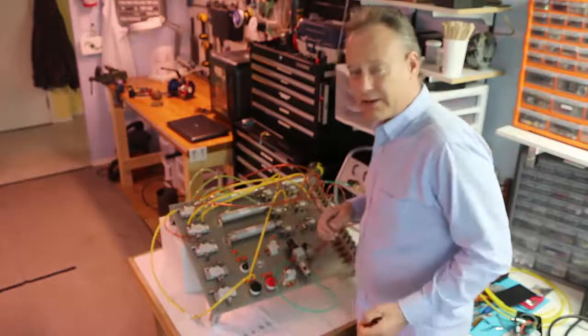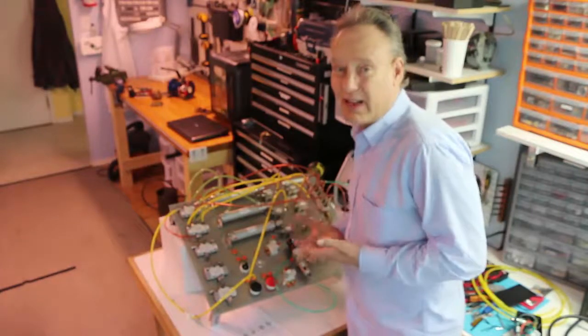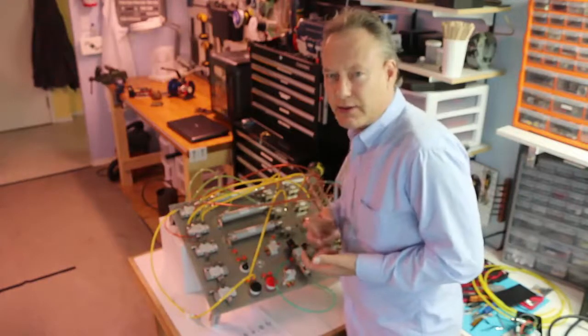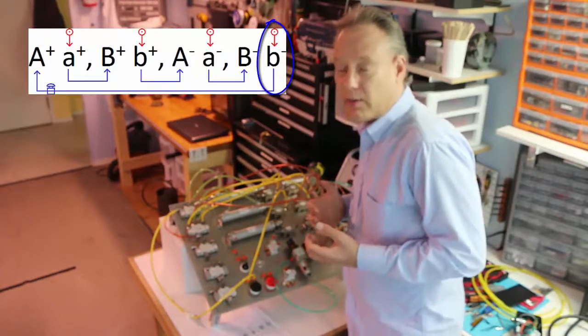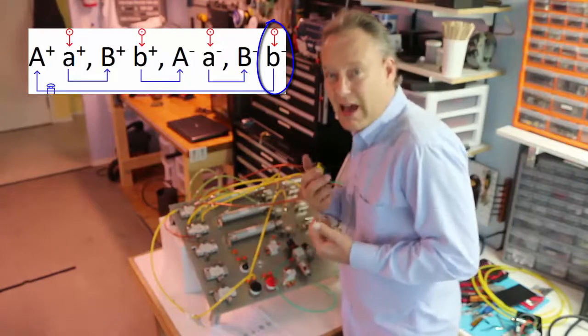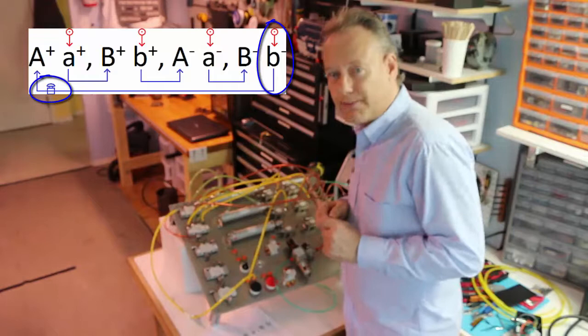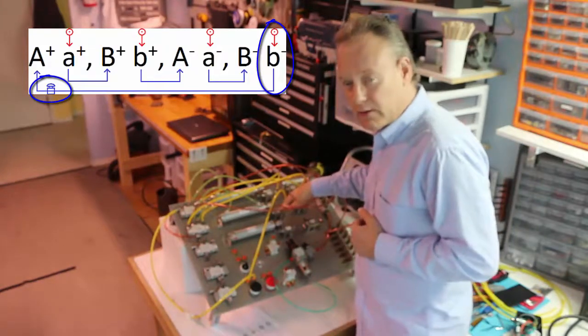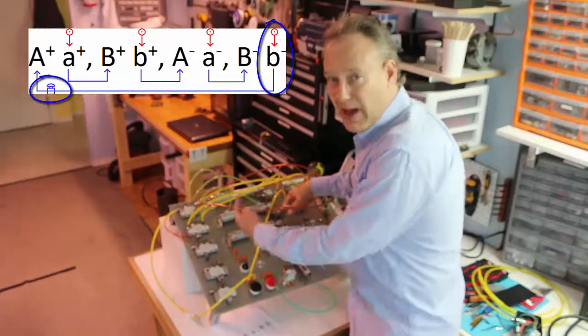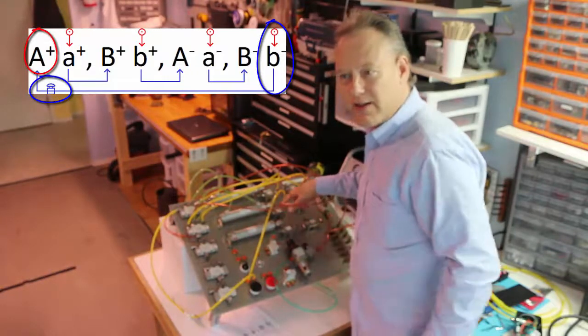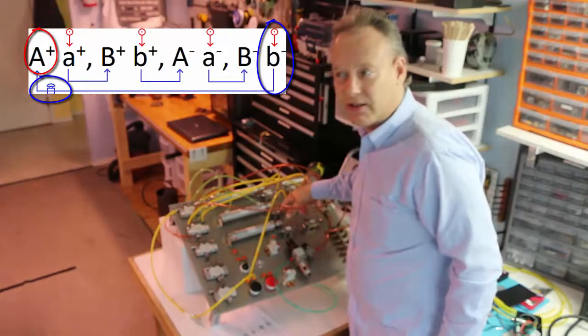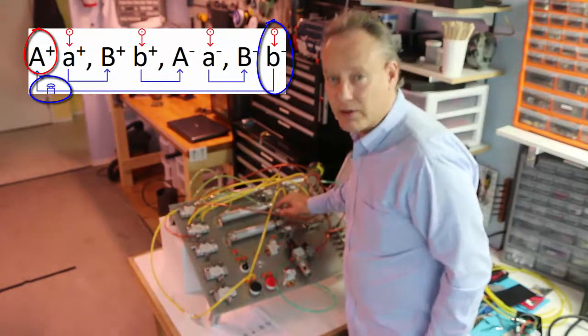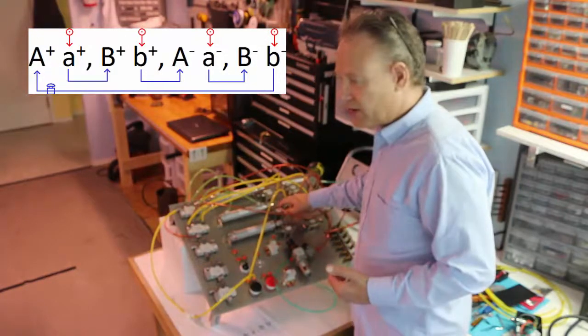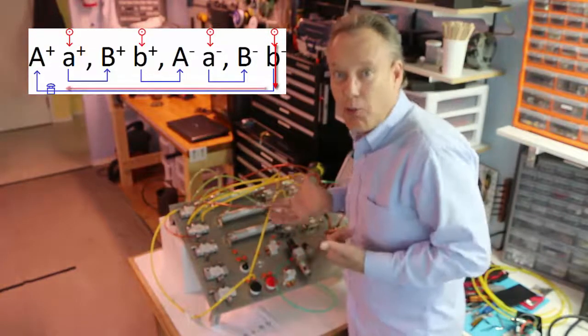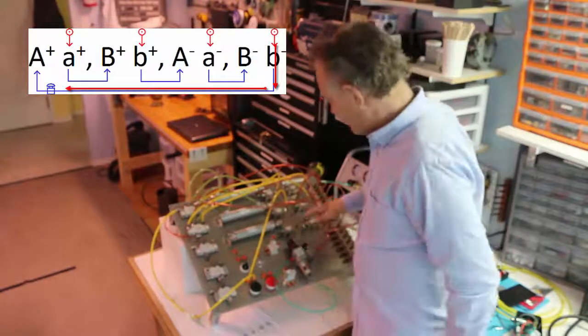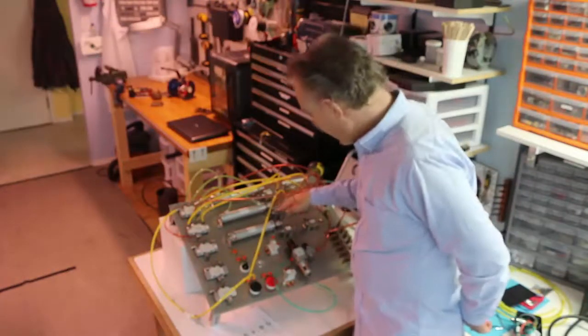So what happens here is that when A goes out, by the way, the thing that tells A to go out is kind of two things. One is the fact that B has retracted and someone pressed the button. If this wasn't retracted and someone pressed the button, A wouldn't go out. And the reason is because the position of B is such that it's at home, and the limit valve, which is like a limit switch, is passing air. It's open because it's been activated. So this guy is at home and that's activated.